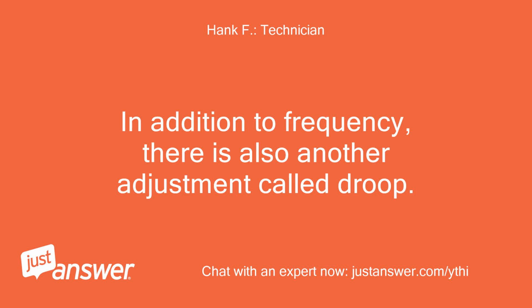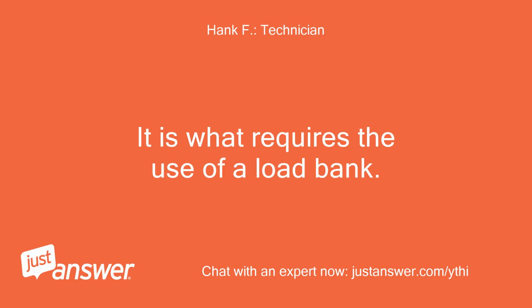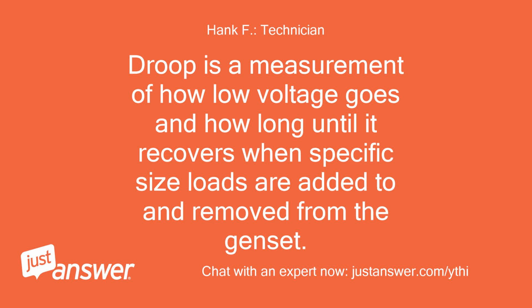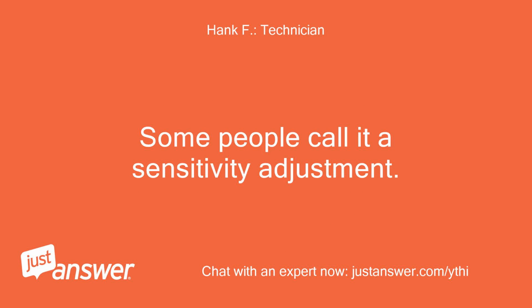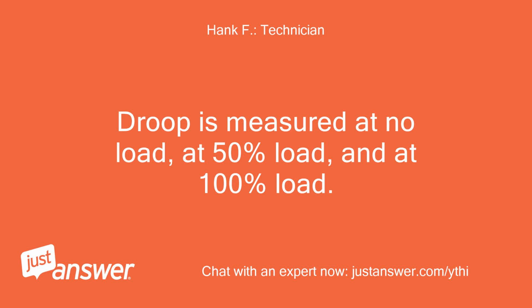In addition to frequency, there is also another adjustment called droop. It is what requires the use of a load bank. Droop is a measurement of how low voltage goes and how long until it recovers when specific size loads are added to and removed from the genset. Some people call it a sensitivity adjustment. Droop is measured at no load, at 50% load, and at 100% load.